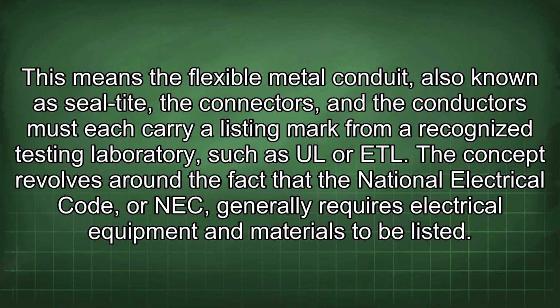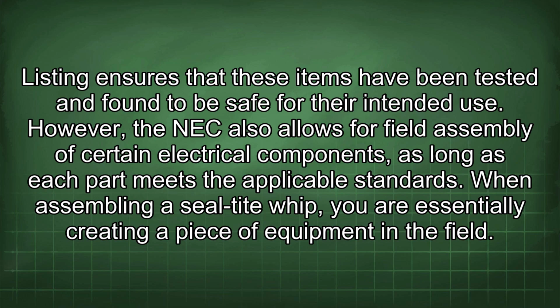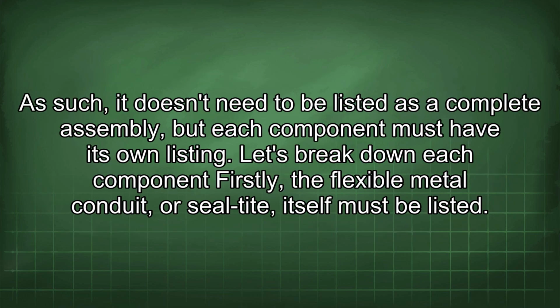The concept revolves around the fact that the National Electrical Code, or NEC, generally requires electrical equipment and materials to be listed. Listing ensures that these items have been tested and found to be safe for their intended use. However, the NEC also allows for field assembly of certain electrical components, as long as each part meets the applicable standards. When assembling a Seal-Tite whip, you are essentially creating a piece of equipment in the field. As such, it doesn't need to be listed as a complete assembly, but each component must have its own listing.